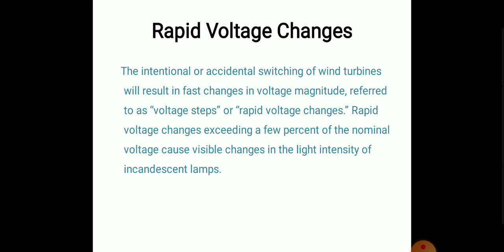That is, if repeated changes in the voltage magnitude result in a short duration flicker value exceeding 1.0 over a period of 1 hour or longer, the majority of persons will consider this uncomfortable when they are using an incandescent lamp, and with respect to other types of lighting people are much less sensitive. Next point, rapid voltage changes of 2% or higher give a noticeable change in the light intensity of an incandescent lamp. Different standards limit the number of rapid voltage changes which exceed 2% to at most several times a day. Rapid voltage changes exceeding 5% should only occur rarely, at most a few times per year.